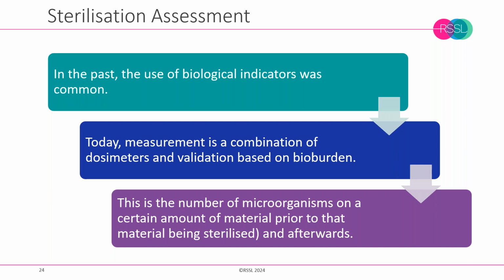In terms of how we would judge the effectiveness of sterilisation, it is possible to use biological indicators, and this may be done by facilities as part of initial setup, but it's more common to assess established product practices through an assessment of product bioburden. So it's an understanding of the numbers and types and relative resistance of microorganisms on items pre-sterilisation compared to the verification of their sterility post-sterilisation.